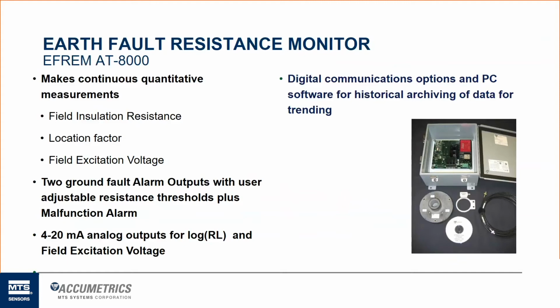We offer 2 ground fault alarm outputs, which are user adjustable. Those come set from our facility at 100K ohms and 2K ohms. So we kind of view that as a warning alarm and then a ground fault alarm. So once the resistance drops below that threshold of 100K, we will send an initial warning alarm to let the user know, you don't have a ground fault yet. However, you are trending in that direction. Time to start paying a closer look at your machine and schedule an outage so you can investigate further and get that damage repaired if needed.